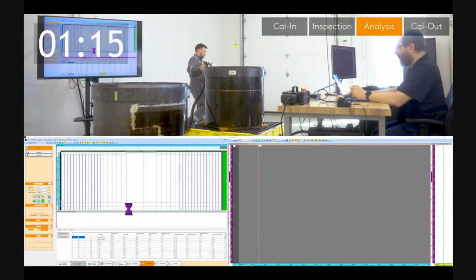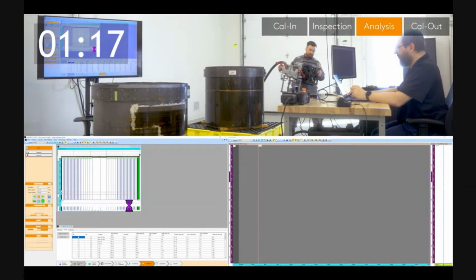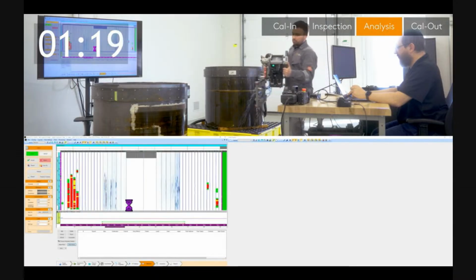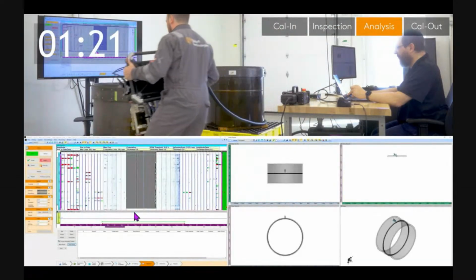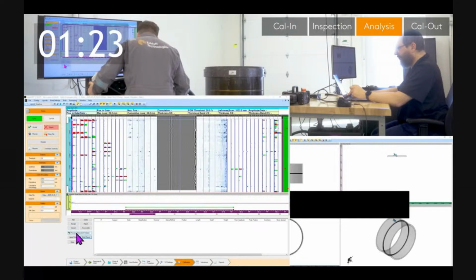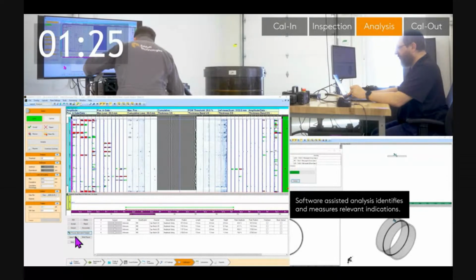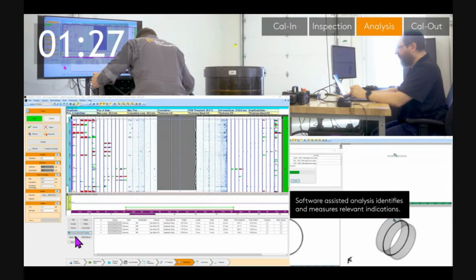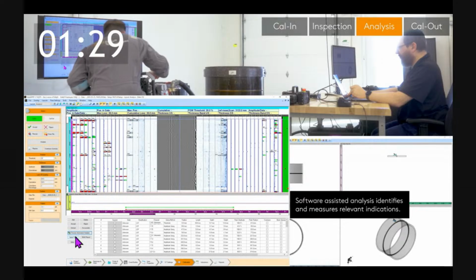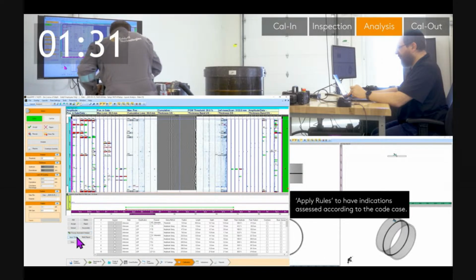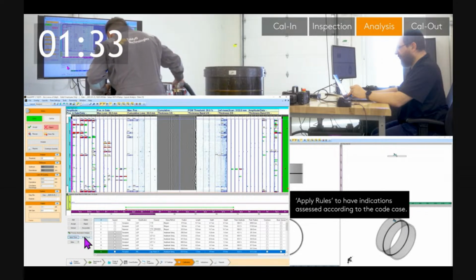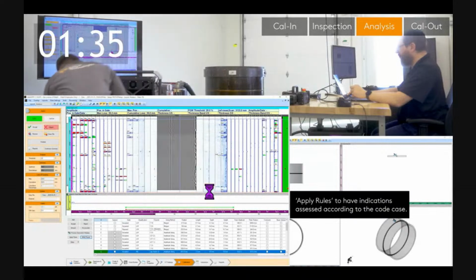I'm going to move the scanner to the cal block again, and Daniel's going to move straight to the analysis step. And we're going to use a rule-based assisted analysis here. So he clicks the button for that. It's going to find everything in the data that meets the rules that we've set, and they're different per type of zone. It's going to flag them, give them a classification code, and measure them and add them to the indication table. The second step happens very quickly.